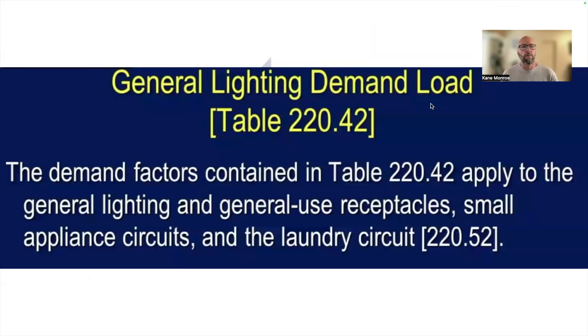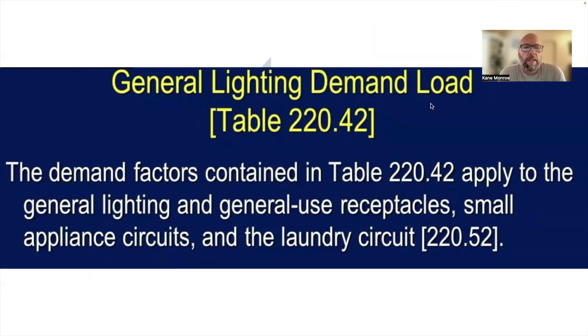When we're doing dwelling units, we have to take into consideration some demand factors based on different items. In NEC 2017, we look at Table 220.42 and apply general lighting and general use receptacles, and in Table 220.52 we add our small appliance circuits and our laundry circuit.